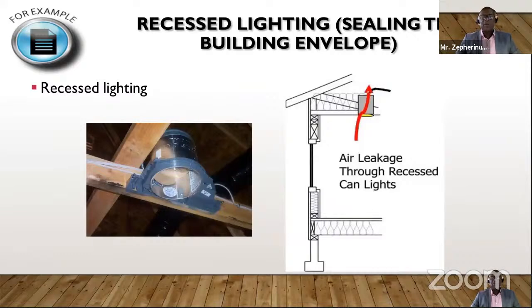Critical is the use of recessed lighting. The code has provisions for using the IC rated recessed lighting. IC rated means it's the insulation contact rated, where the canister, it's double canned. So the recessed light is double canned, meaning that you can now have the recessed light in contact with the dry wall. There is no need to have a gap of about 3 inches between the recessed light and the dry wall.